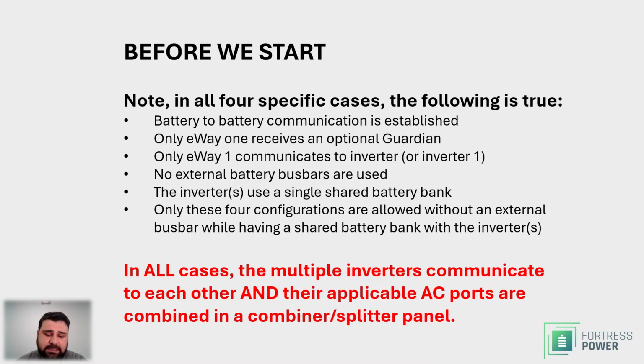So the idea is that even if you have multiple eWays, i.e. multiple eForce stacks, the eWays communicate to each other, and the primary eWay number 1 collects all the data and communicates that data to the inverter. No external battery bus bars are used. As I said, these are 4 cases specifically which are 4 configurations with no external bus bars, although there are multiple batteries and multiple inverters.